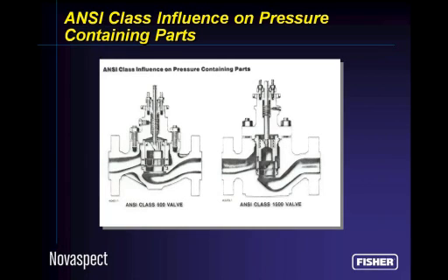The difference between two control valves that are designed for two different ANSI classes essentially is a matter of wall thickness. You can see the picture on the left is the ANSI class 600 valve. That valve has very thin walls compared to an ANSI 1,500 pound class valve. Obviously, the valve on the right, the 1,500 pound class valve, is designed to handle much higher coincidental pressures and temperatures from the design basis.